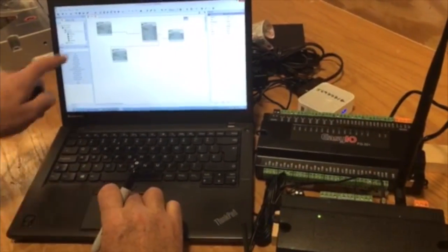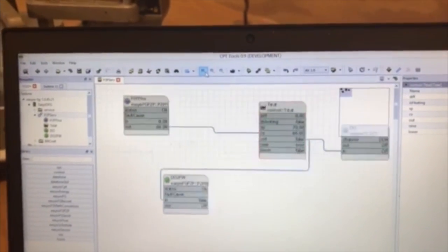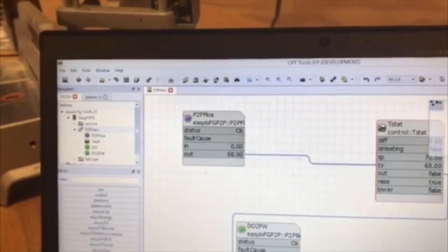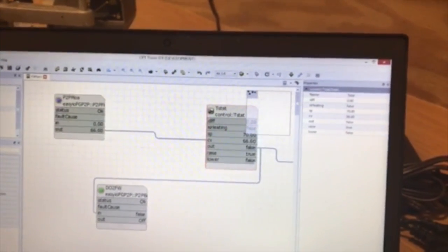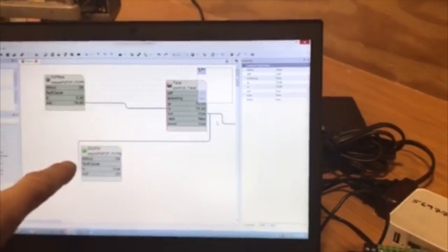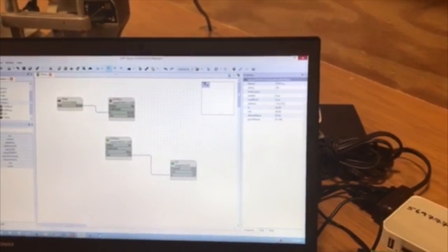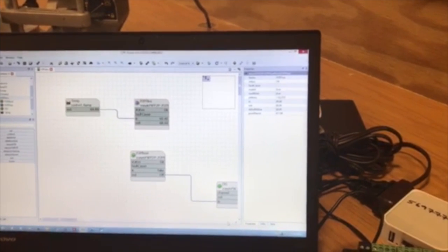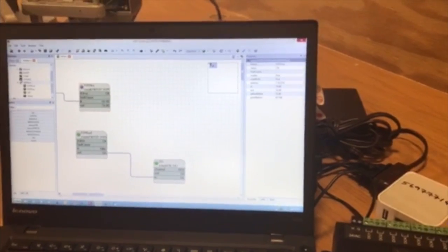If I go to the FG, I can show you it being received here. I'm running it into a thermostat object. You can see this is coming from the FW to the physical FG32+ into the thermostat. I've set a setpoint of 70 and I'm switching a relay, which you can hear clicking on and off in the FG32. I'm then sending the same output back through the peer-to-peer network into the FW, and you'll see this relay clicks on and off in the FW as well. Of course, in real life you probably wouldn't do that, but it's good to show you what is possible.